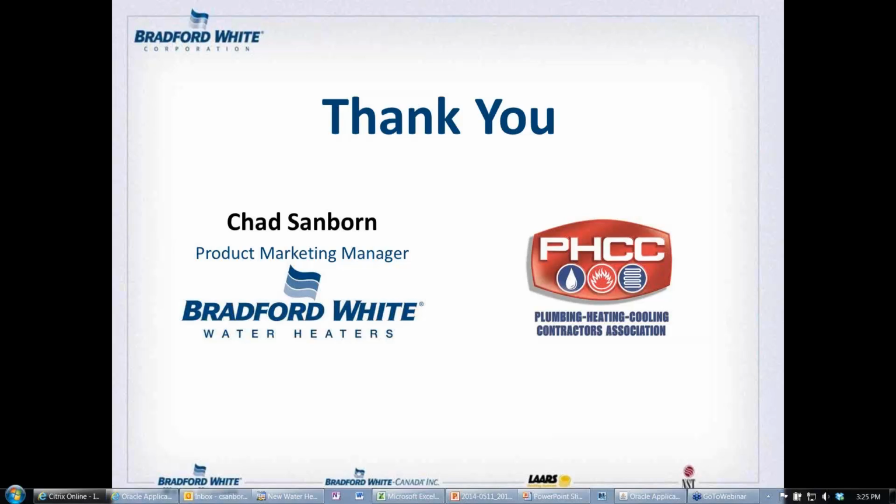Another question. Please explain again why the units below 55 gallon will need to be expanded with insulation. So as the energy factor increases, the way to achieve a higher energy factor is to keep the heat inside the tank or in the water and not letting the heat escape through the jacket of the water heater. If we need to increase the energy factor, the way to achieve that is to increase the insulation. So you're adding insulation to the water heater.